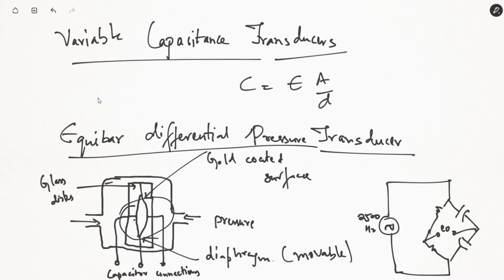Now its principle is simple. This only measures differential pressure. That means if pressure is more on one side and less on the other side, the way the diaphragm changes will result in a capacitance that causes an imbalance in this bridge, that will result in an output voltage.